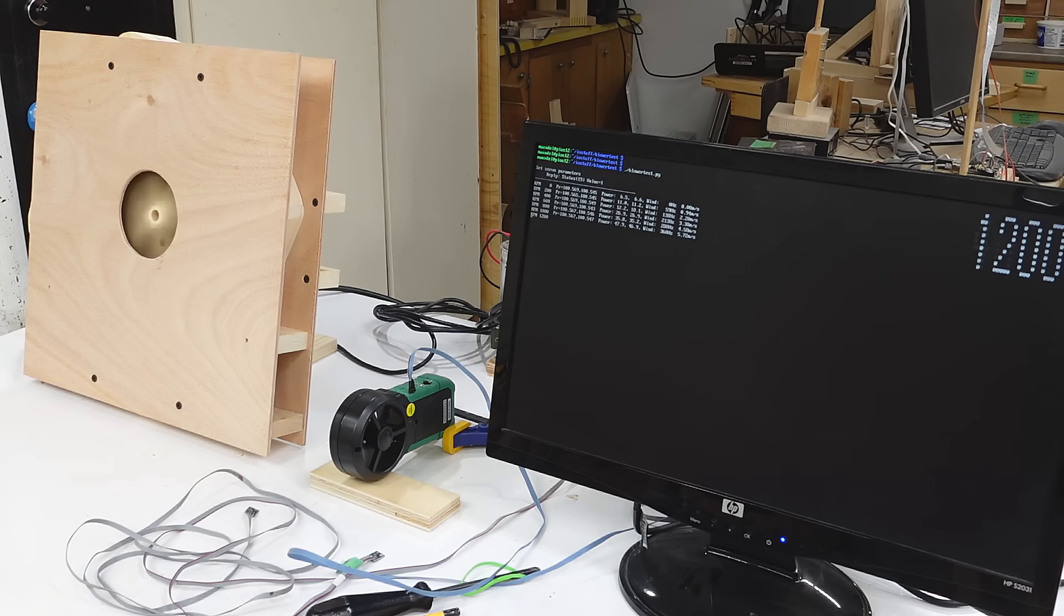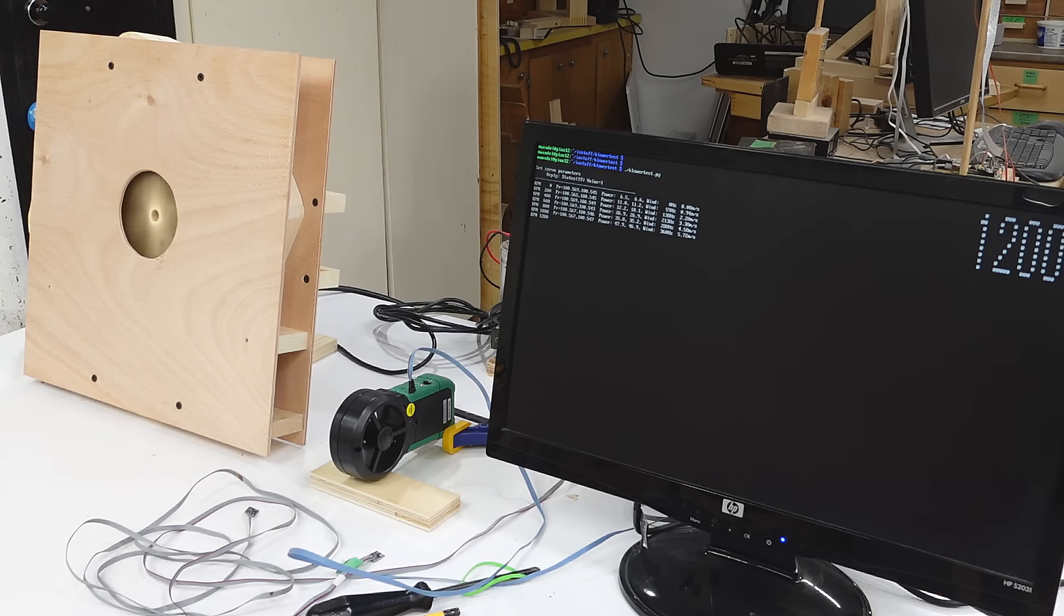I'm slowly stepping up the RPM in steps of 200 RPM and then speed, pausing for a while to stabilize, and then taking anemometer and pressure and power readings.